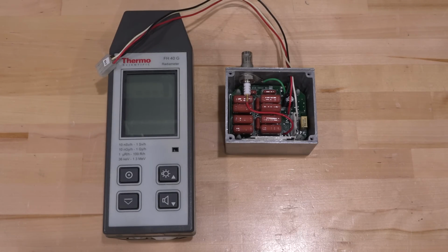I took a look at the preamp signal directly. Absolutely nothing. Now there are many reasons why this could happen. For example, we may have no X-ray at all, or the X-ray shutter may be broken. In that case, X-ray will never hit the sample. There will be no fluorescence. There will be nothing to detect.